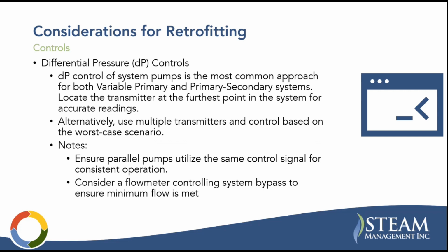Hey Chase, we have a question in the chat. This might have been a few slides ago. It says, where can thermal storage fit well with this strategy? The best place to install your buffer tank is in your decoupler line, and the buffer tank basically acts as your decoupler. It gives your primary loop that thermal inertia, and it's just kind of a recommended location. I mean, you can make an argument to install it in other places, but that's kind of the tried and true location on a primary secondary system.